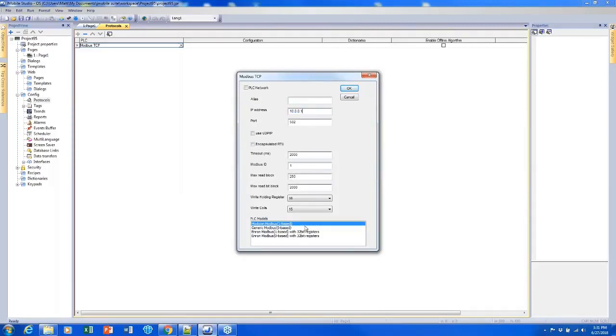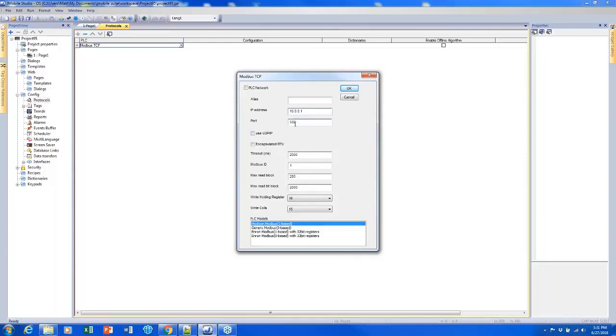I can select whether it should be 16-bit based registers or 32, which usually it's going to be 16. I can select if addressing should start at 0 or 1. I can change the port as well, even though it will usually be 502.